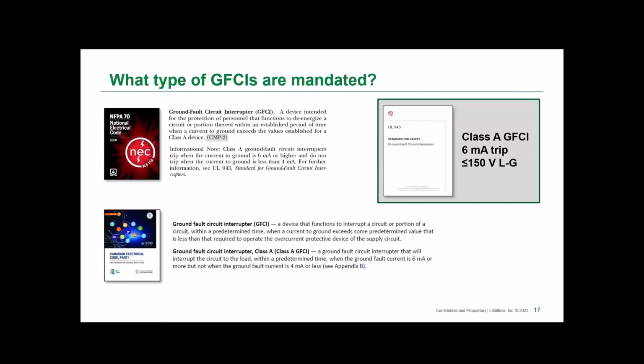And in Canada, there has been a definition that referred separately to a GFCI and to a Class A GFCI. But speaking in practical terms, the Class A GFCIs were really the only ones specified in the Canadian code as well. So these devices were mandated in homes and in commercial buildings and workplaces. But as we talked about, this is for devices 150 volts, line to ground and below. So it covers the handheld small tools and circuits, but it does not cover the high voltage circuits or the higher voltage circuits used in many production or industrial facilities.